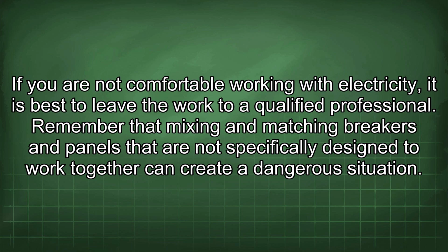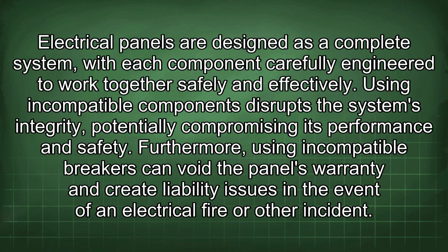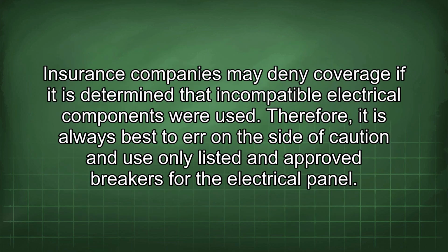Remember that mixing and matching breakers and panels that are not specifically designed to work together can create a dangerous situation. Electrical panels are designed as a complete system, with each component carefully engineered to work together safely and effectively. Using incompatible components disrupts the system's integrity, potentially compromising its performance and safety. Furthermore, using incompatible breakers can void the panel's warranty and create liability issues in the event of an electrical fire or other incident. Insurance companies may deny coverage if it is determined that incompatible electrical components were used.